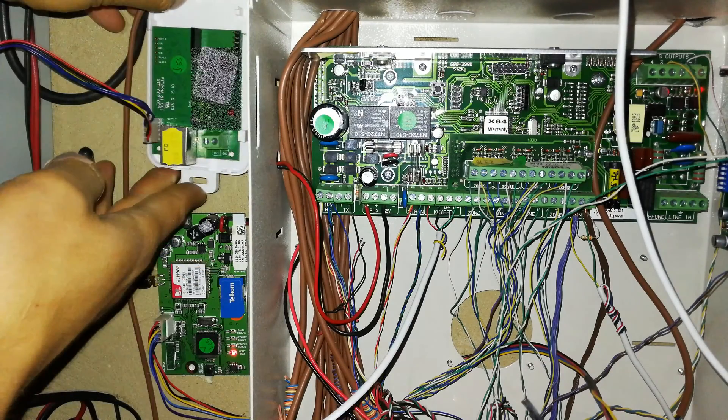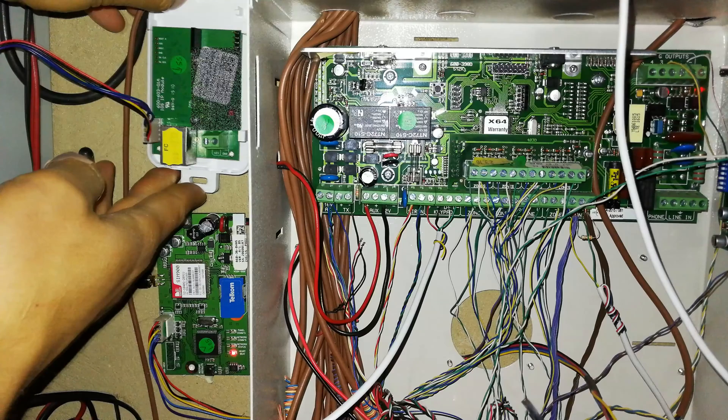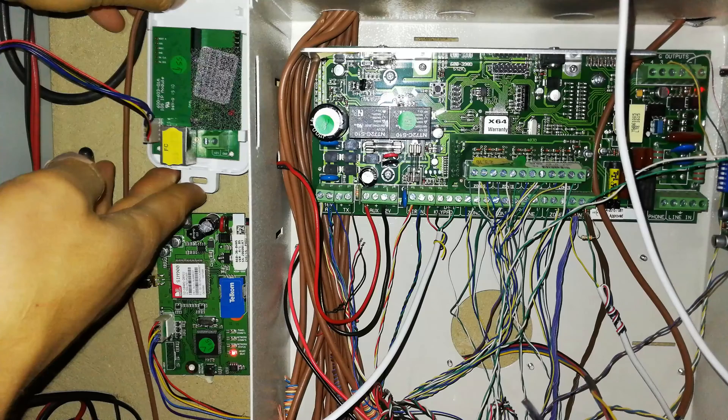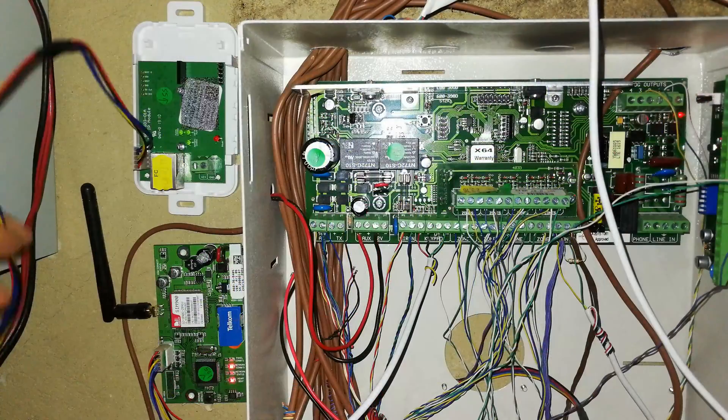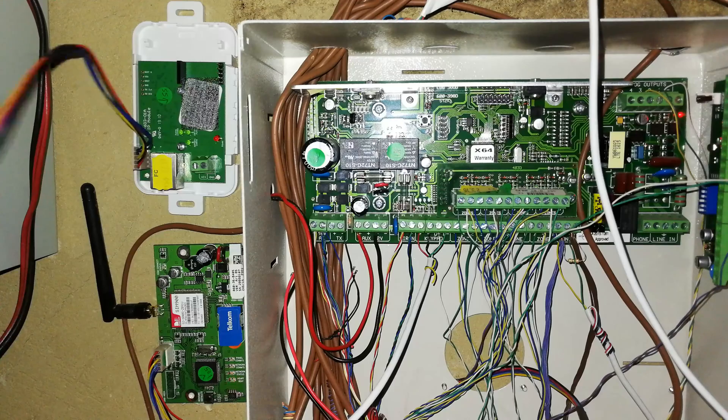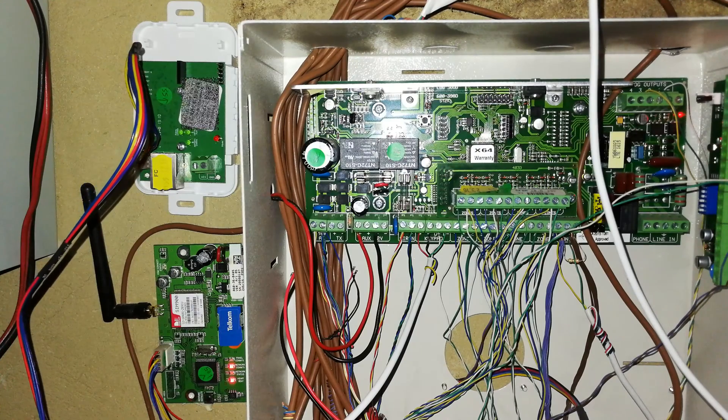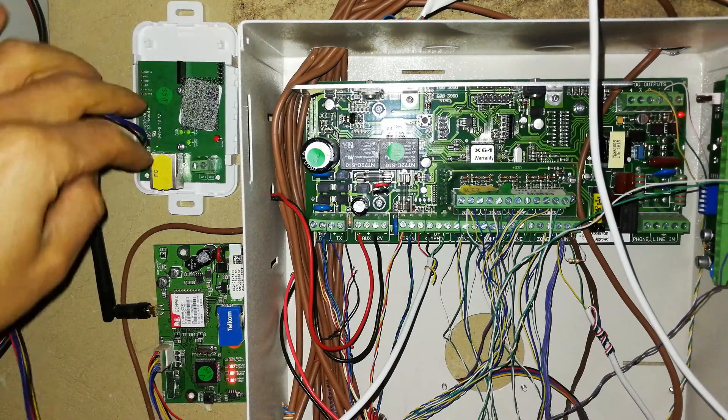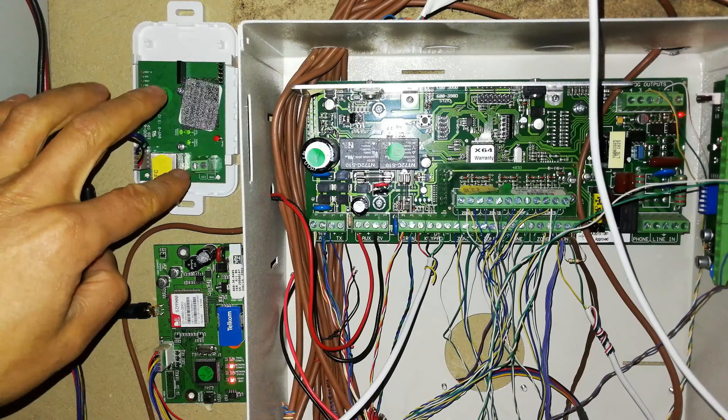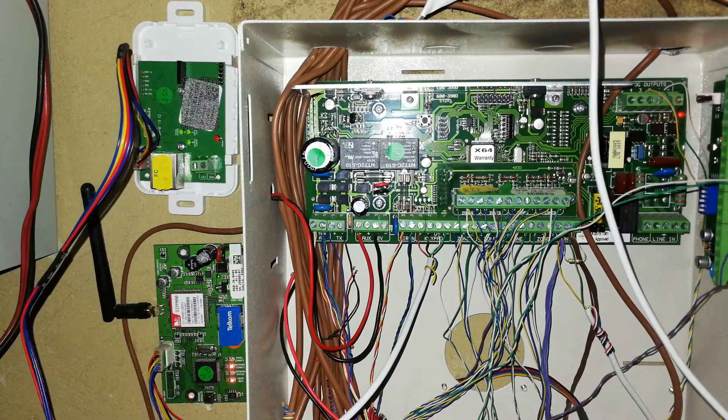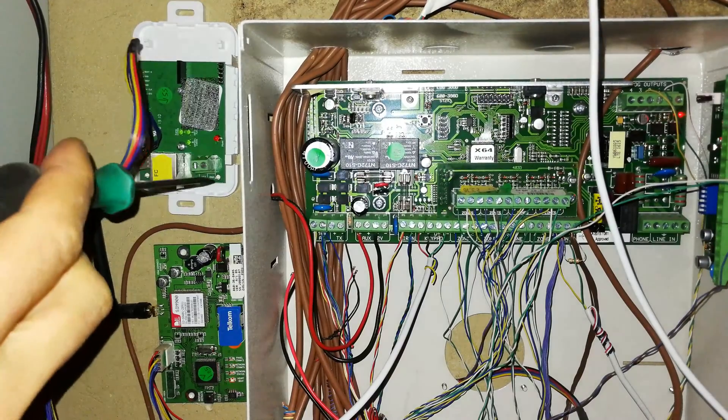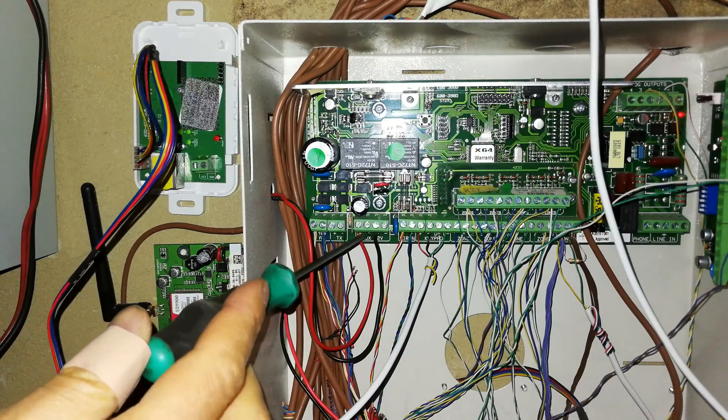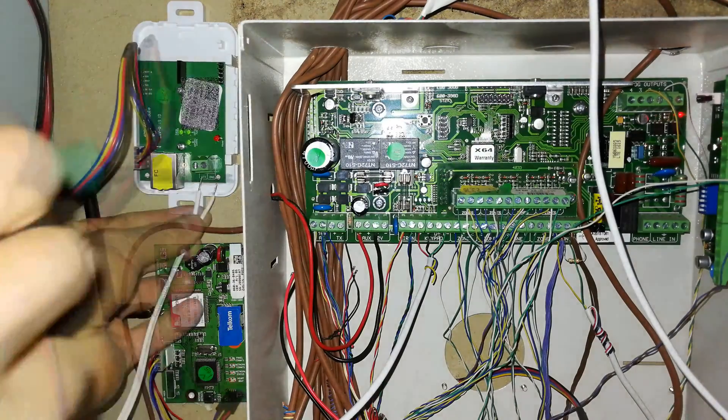All right, the bottom is where the RJ45 port is, and I'm going to stick this next to the panel. It needs to be plugged in, but before I plug it in, I'm actually going to power it up. So I have a fly lead here and it needs 12 volts. The ground is on the right hand side and the 12 volts is on the left hand side. My experience with the IDS is that it's probably best to power it directly from the alarm panel power output itself rather than using an independent supply.